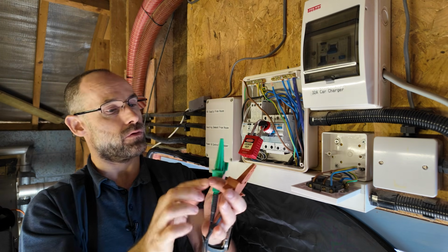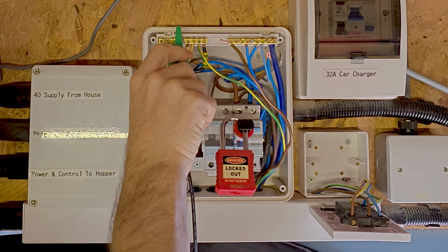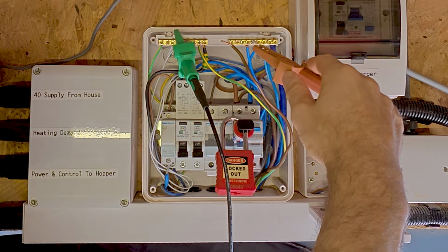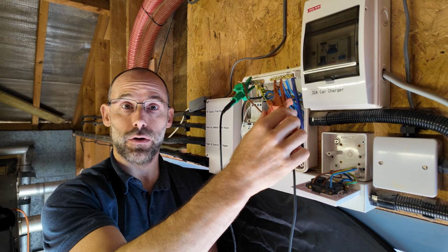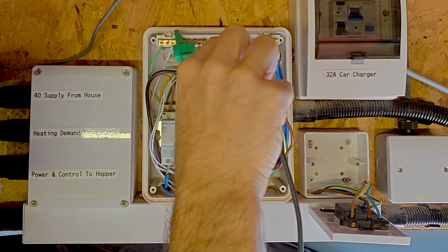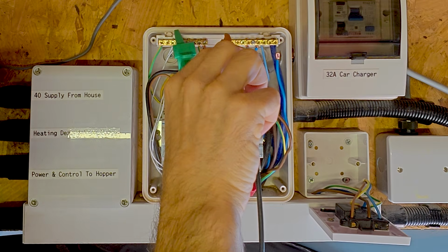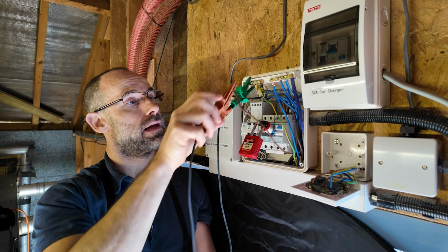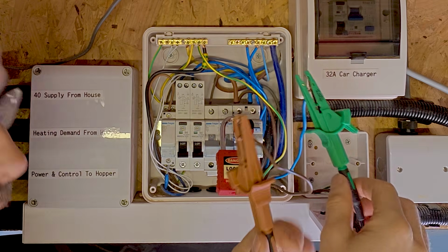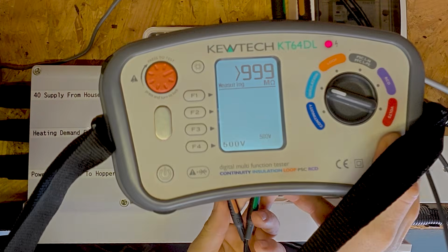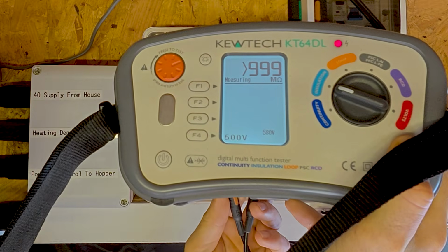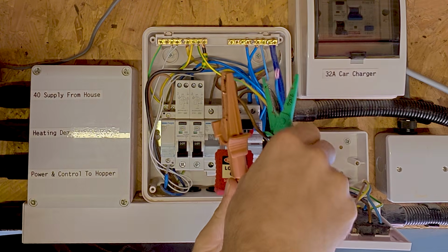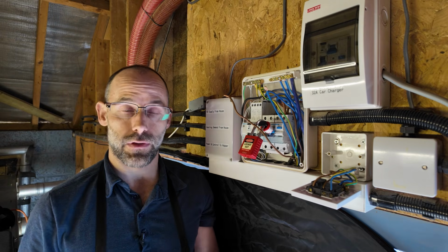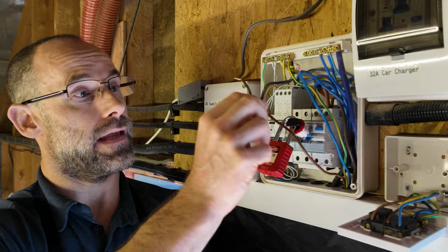So what I do is I want to do the tests on all the possible combinations. So I can come to the earth, or the CPC, to neutral, and I see I have more than 1 billion ohms of resistance. So the insulation between those two is good. Between the CPC and the line conductor, I have also more than 1 billion ohms. And then when I come between line and neutral, which is the third possibility, also more than 1 billion ohms. I'll just show you the screen of that just for fun. You can see what I mean by that. It says greater than 999 mega ohms, greater than 999 million ohms. That's it. That is the insulation resistance test done, confirming that the insulators are doing their job.